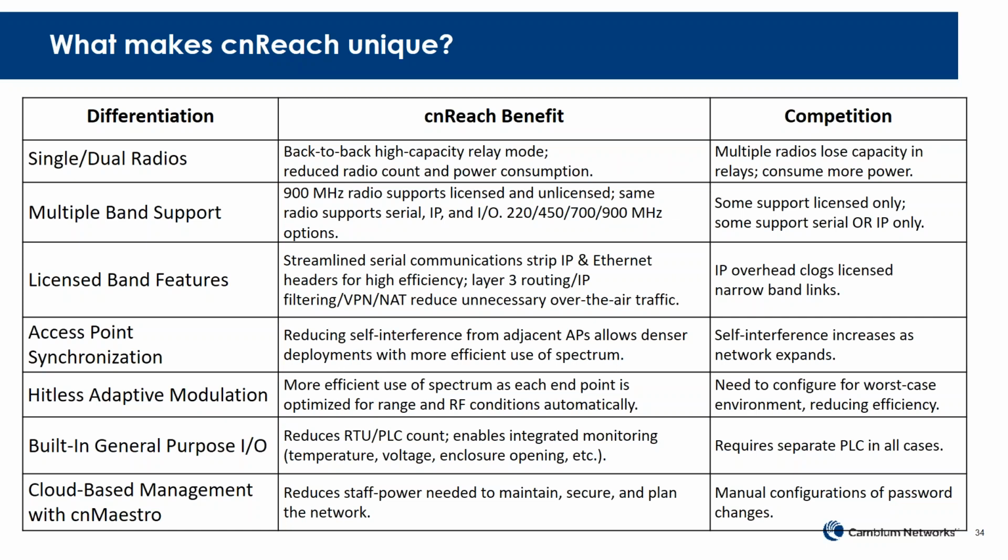On licensed spectrum, oftentimes the polling is done in a round-robin fashion so that you are really controlling it. Let's say I have 30 devices or 40 devices on an access point. I can step through and poll one after another in series, and that prevents the overloading of the network and allows you to scale up. So there's not a real theoretical limit on how many endpoints you can put on an access point, but in practice, we suggest 50 to 70 as a rule of thumb.